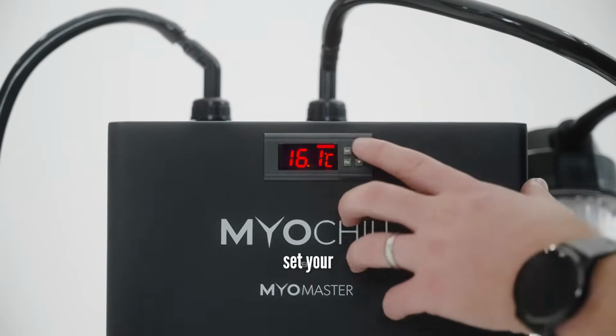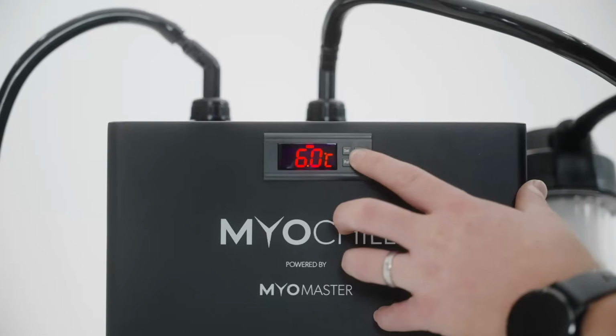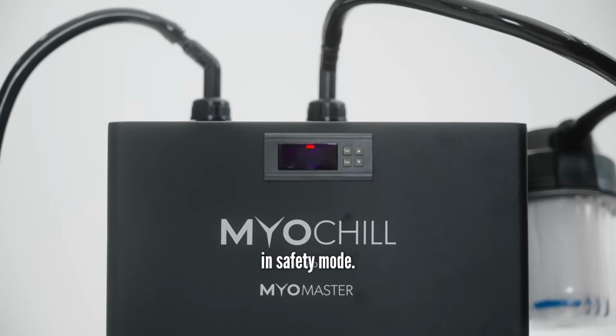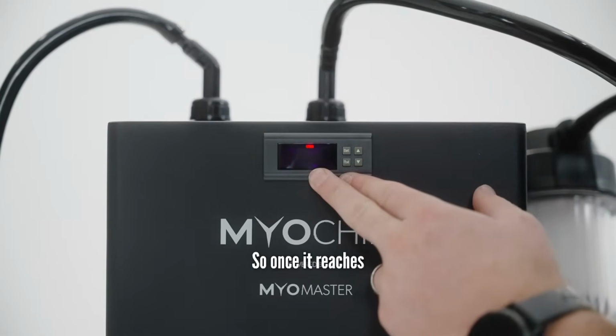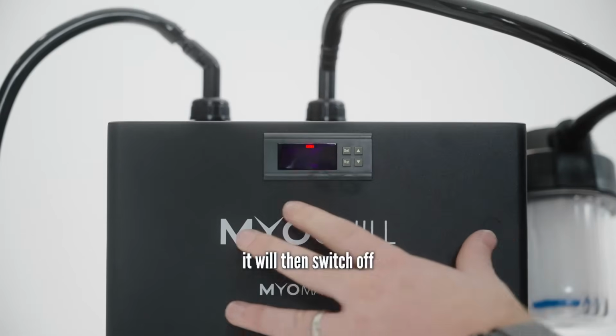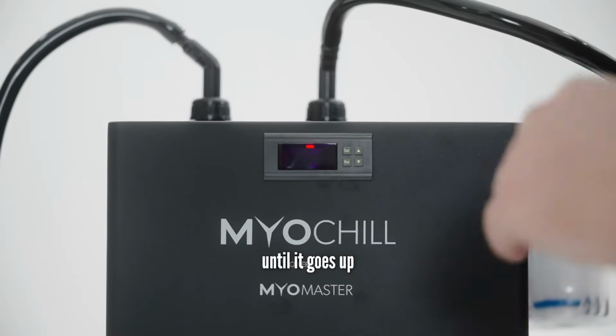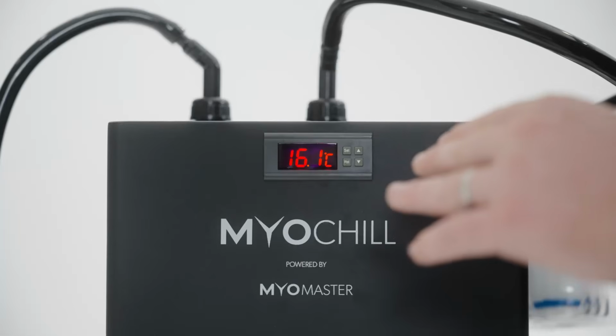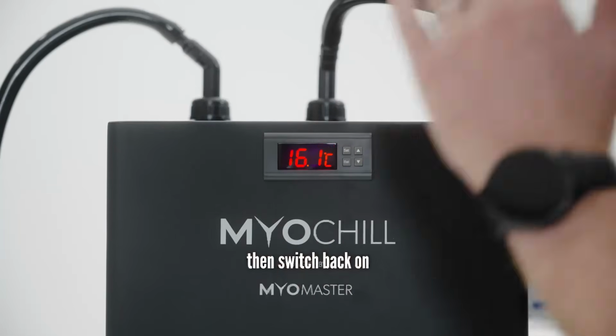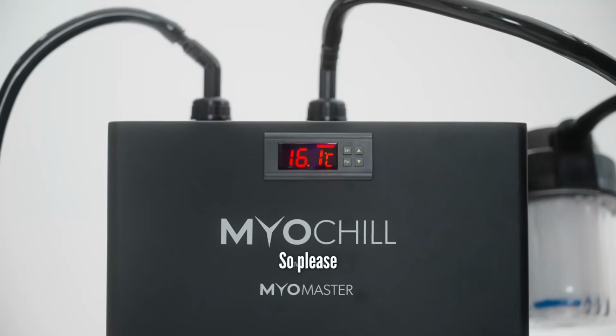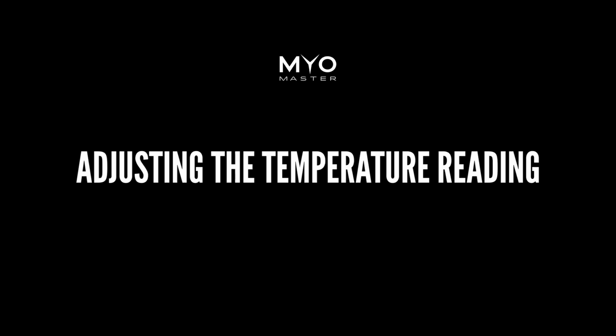Please be aware that when you set your desired temperature, the chiller has a built-in safety mode. So once it reaches 6 degrees, it will then switch off chilling to let the chiller recover until it goes up by 2 degrees. Once it reaches 8 degrees, it will then switch back on and bring it back down to 6 degrees. So please make sure you take this in mind when setting your desired temperature.